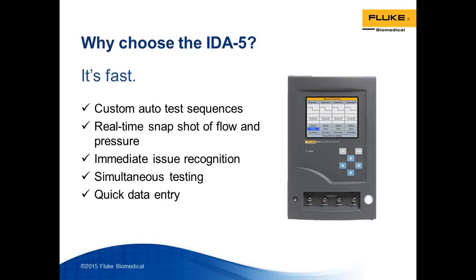It's fast. It has custom auto sequences, like I just mentioned. It gives you a real-time snapshot of flow and pressure, and this is very important because you really don't want to wait till the end in case there is a spike while you are testing flow. You want to know immediately. So it's got a real-time snapshot with a graphical display that will show you exactly how the infusion pump is performing, which means you have immediate issue recognition instead of after the fact. The simultaneous testing we already talked about, and the fact that we have plug-and-play accessories where you don't have to feed information in. You can barcode it in, or you can use the keyboard to enter the data.